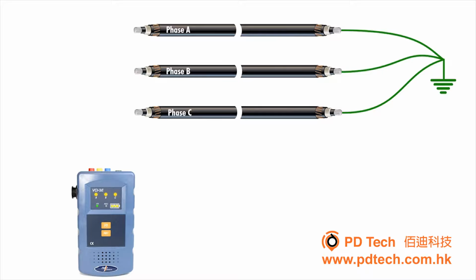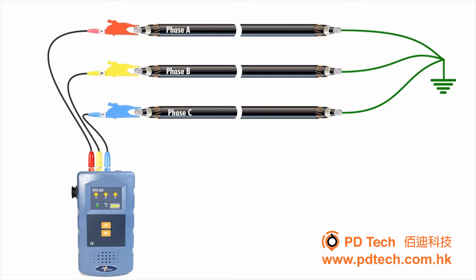For direct injection method, install the leads on the top of the transmitter and connect the clips to the cable conductors. Make sure to match clip A, B, and C with the corresponding cable phasing, as it will later be necessary for phase identification applications. Incorrect transmitter phase setup will yield incorrect phase identification.